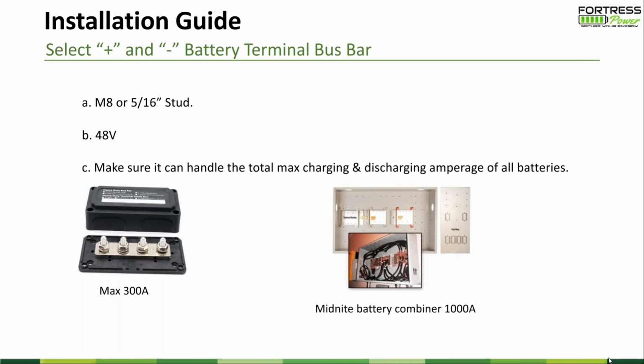We recommend that you use a combiner if you have a bigger system. A lot of customers install 10, 15 batteries in the same solar system. So you can use the bus bar, the bus combiner. We always use Midnite a lot of times. It goes up to 1,000 amps. It's pretty easy for installation, and saves you a lot of time. But if you have a different situation, you can use a homemade bus bar tool, which is available in the market. You just need to drill a few holes and make sure you isolate it from metals and moisture. That will work too. Next slide, please.